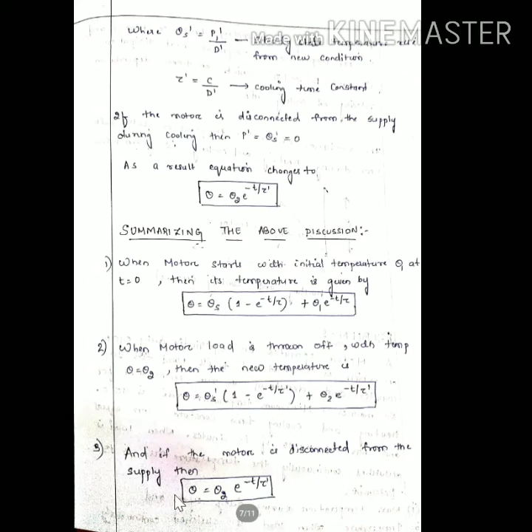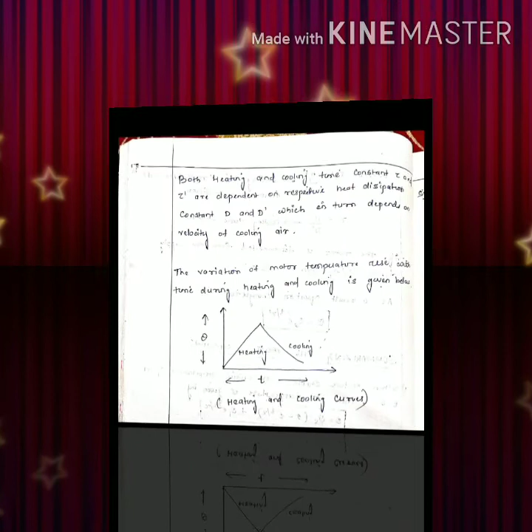When motor load is thrown off with temperature theta equal to theta 2, then the new temperature is given by theta equal to theta s dash into 1 minus e to the power minus t by tau dash, plus theta 2 into e to the power minus t by tau dash. And if the motor is disconnected from the supply, then we get theta equal to theta 2 e to the power minus t by tau dash. Both heating and cooling time constants tau and tau dash depend on respective heat dissipation constants, that is D and D dash, which in turn depend on the velocity of the cooling air. The variation of motor temperature rise with time during heating and cooling is given below.